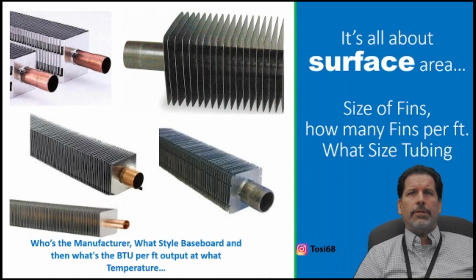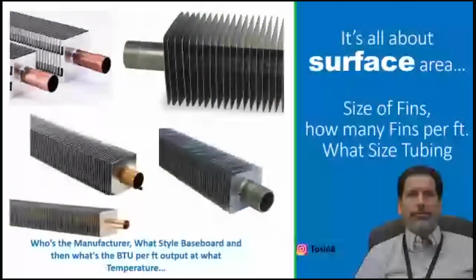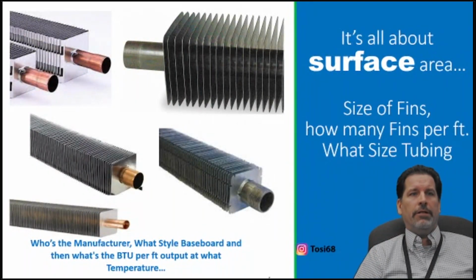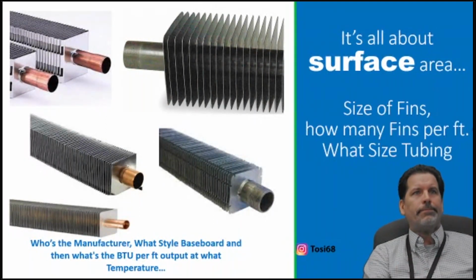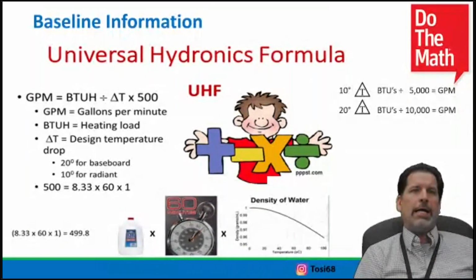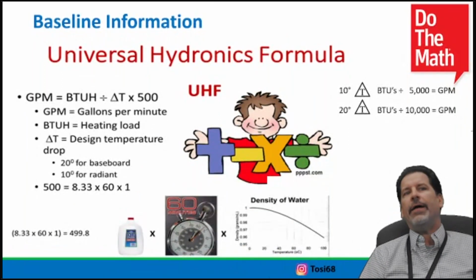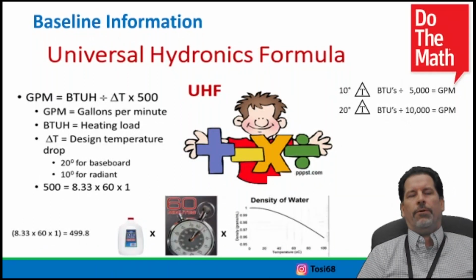All right. So again, surface area is key. Size of the fins, how many fins per foot, what size tubing, right? We're delivering BTUs. We're not delivering temperature, right? So again, based on manufacturer, the style, and BTUs per foot, and they have water temperatures. Different water temperatures will give us those delivered BTUs. Again, a little baseline information here as we talk about doing the math, right? Seems really scary and a waste of time, but it's everything you need to start with.